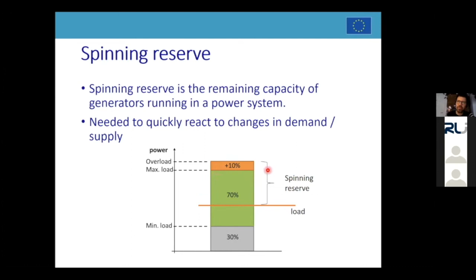The N+1 reserve is to make sure that if one generating unit, usually the largest, fails, the remaining units should be able to cover the current load. And here's a brief example of what we mean with that. If you need to supply 1.2 megawatt and you have 4 500 kilowatt units, I make a brief test. I'm not sure if you can use the chat for this, but 4 500 kilowatt units are 2 megawatts. So if one unit fails, the remaining is, yeah. So I think you have the answer. The remaining is 1.5 megawatt. So you would still be able to supply the load.